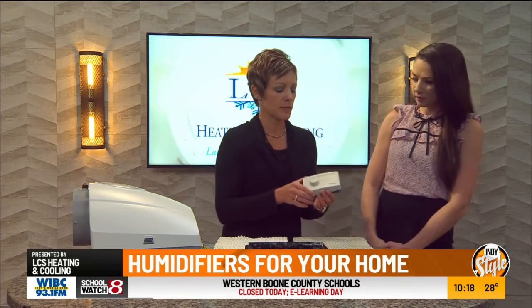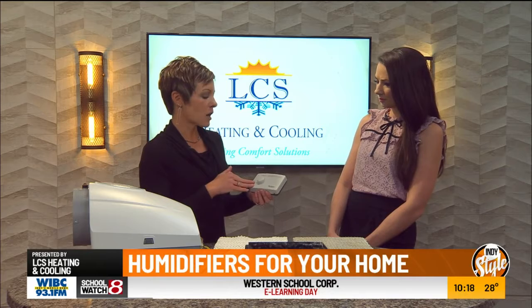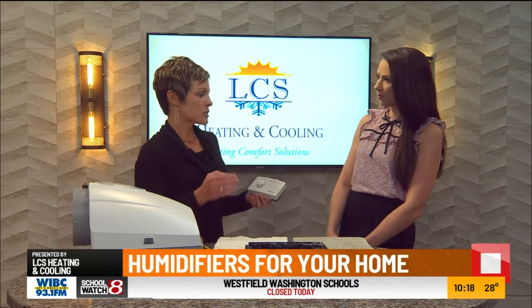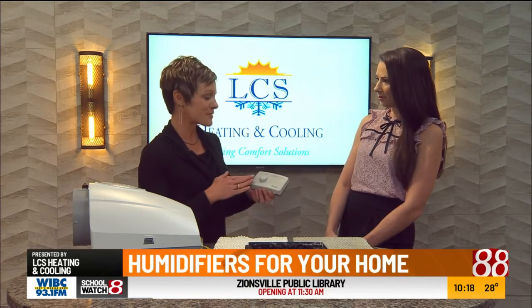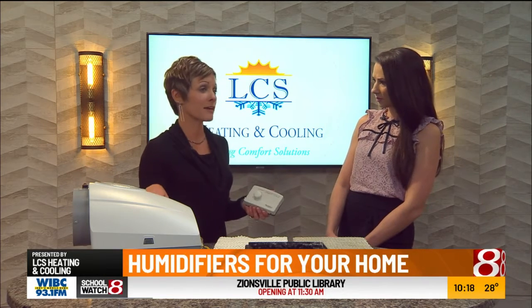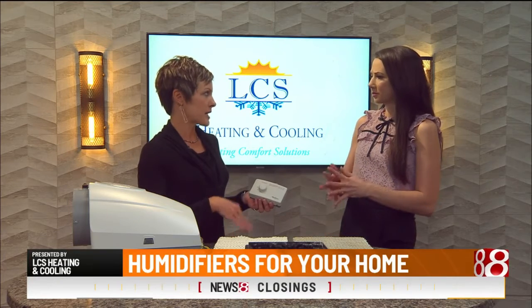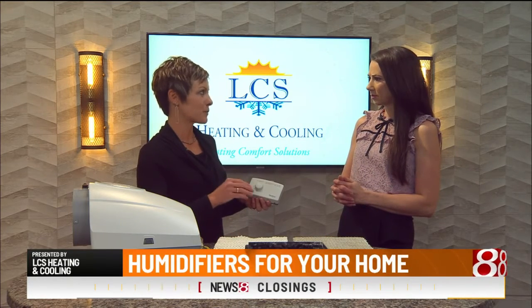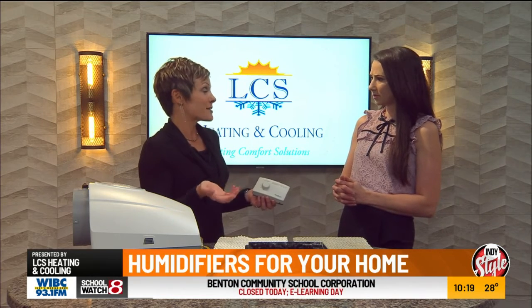This is the humidistat. People often ask what humidity level they should have in their home. It's going to depend on the temperature outside. If it's 40 degrees — and we've had a lot of those days this winter — you might easily get 45% humidity in your home. However, when it's 20 or 10 degrees, you can expect more like 30 to 35% to be what you really want to achieve.